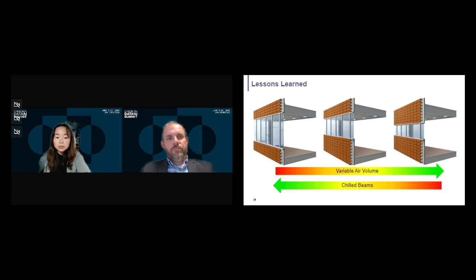So this is a lesson learned in the past where we have the active chill beam system versus the variable air volume system. We have active chill beam system downstream from the DOAS system as the decoupling of ventilation and cooling. And traditionally, we will use a variable air volume box, which can turn down the airflow and help with the building overall consumption. So in the past, we learned that depends on your overall glazing percentage, glazing performance, your latent load, your ventilation requirement, your air change requirement, chill beam can sometimes be less energy efficient compared to a traditional variable air volume system.